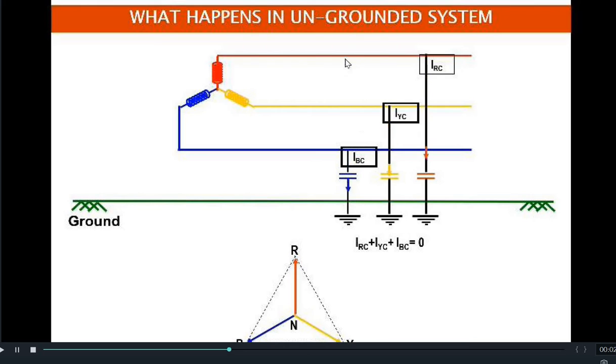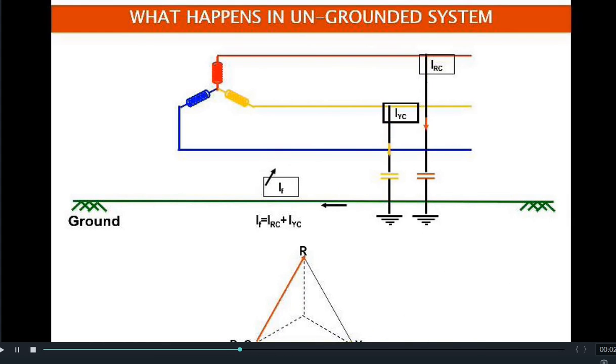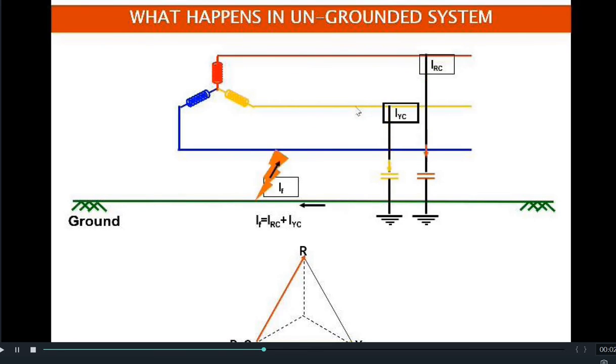The phase voltages to neutral are R, Y, and B. Now if there is a fault in the B phase, the potential of the ground becomes the potential of B phase. So the phase voltages of R and Y, which were earlier phase-to-neutral, will now become phase-to-phase voltages with respect to ground or neutral.